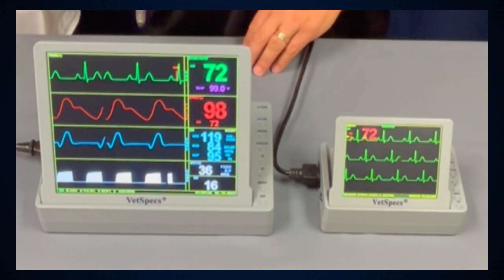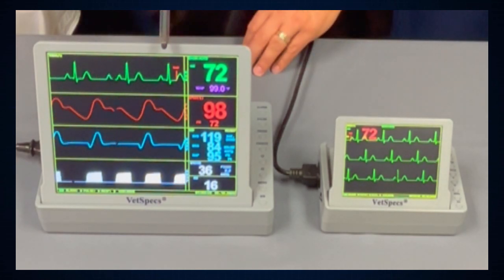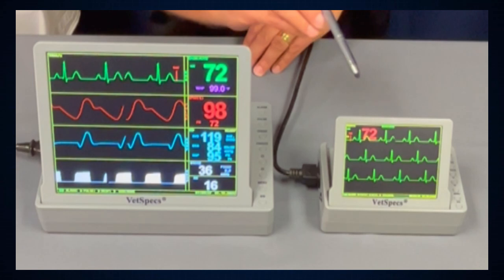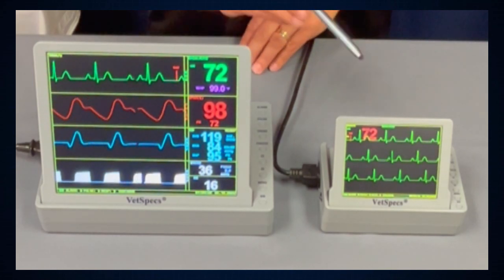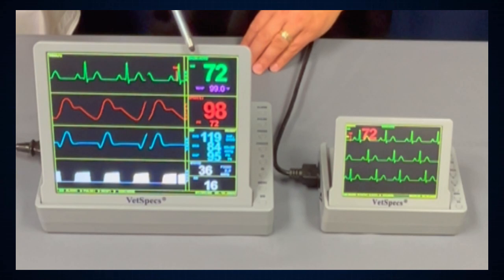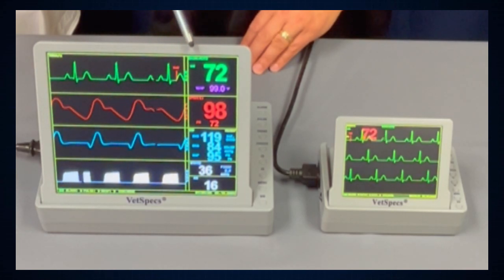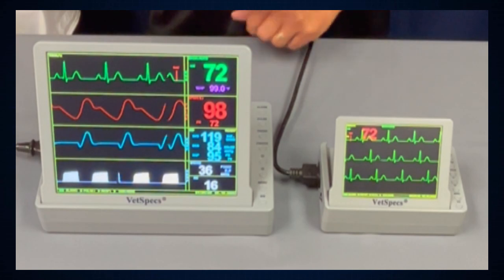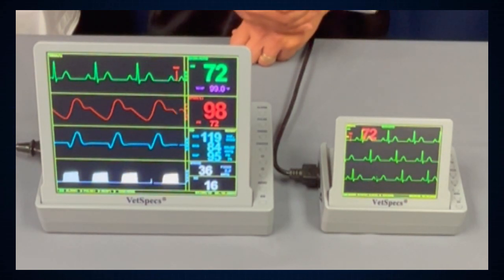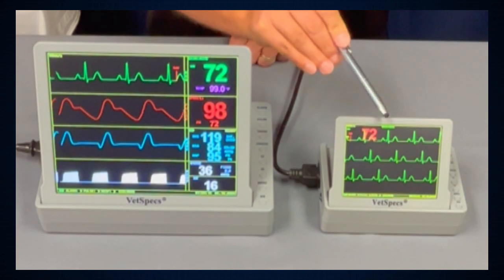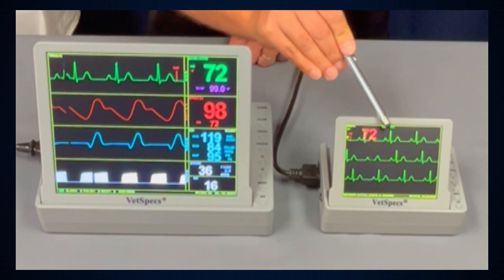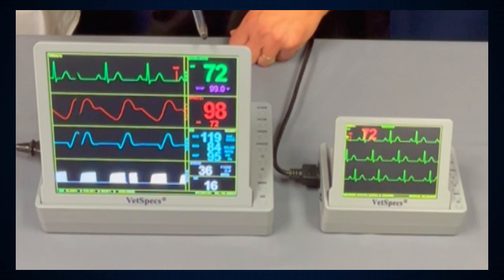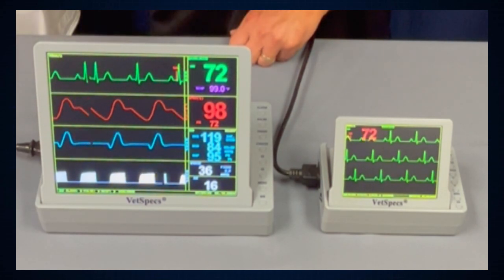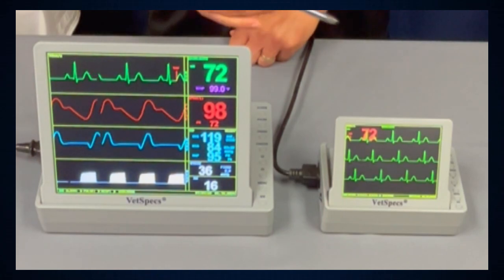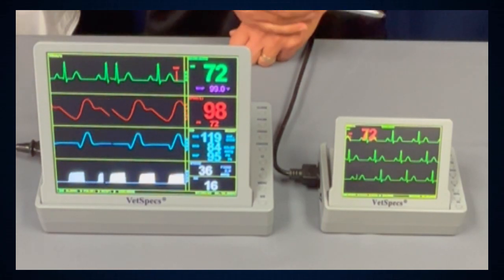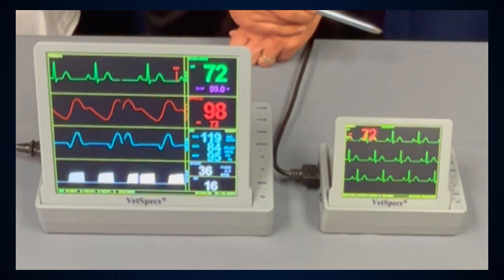Before we get started in on the actual external components for the ECG, I did want to bring your attention to the two different display modes that you're seeing here. It's important to note that both the WM100 and WM10 platforms can either show the ECG only mode or the multi-parameter or all-parameter mode. It does depend upon what you have connected to the patient. So for instance, if you have only ECG lead wires attached to the patient's body, the monitor will go right into ECG only mode. If you have ECG lead wires or esophageal probes, plus any other function such as temperature, SpO2, CO2, the monitor will automatically go into multi-parameter or all-parameter mode.